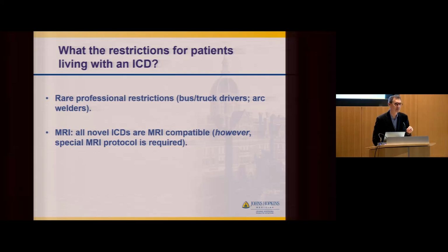It's a little bit more difficult to get MRIs with a defibrillator. The problem is that there's no ICD that is labeled by the FDA as MRI safe. The labeling by the FDA is only MRI conditional, which means, yes, you can have an MRI, the device will withstand that. However, it needs to be turned off before you go into an MRI scanner. You need to be monitored when you're in the MRI scanner. It needs to be turned on again when you come out. And that's more labor intensive. It's more personnel intensive. We can do very few studies during the day. And there's a long wait list to get in if you have an ICD and you need an MRI.